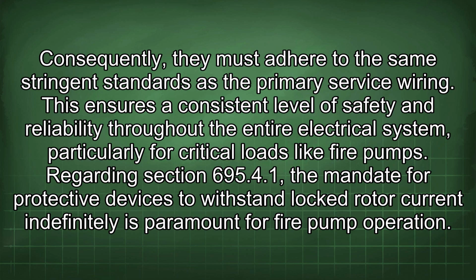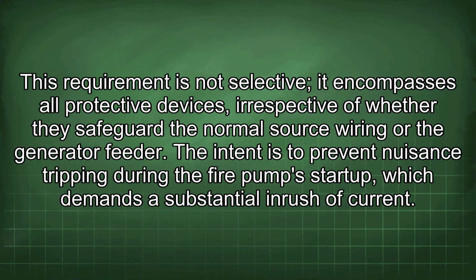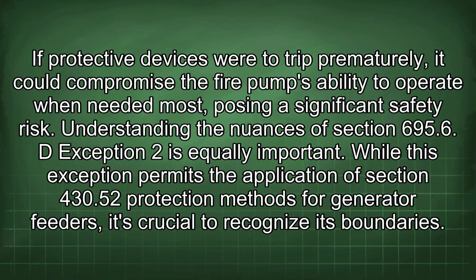This ensures a consistent level of safety and reliability throughout the entire electrical system, particularly for critical loads like fire pumps. Regarding section 695.4.1, the mandate for protective devices to withstand locked rotor current indefinitely is paramount for fire pump operation. This requirement is not selective, it encompasses all protective devices, irrespective of whether they safeguard the normal source wiring or the generator feeder. The intent is to prevent nuisance tripping during the fire pump startup, which demands a substantial inrush of current. If protective devices were to trip prematurely, it could compromise the fire pump's ability to operate when needed most, posing a significant safety risk.